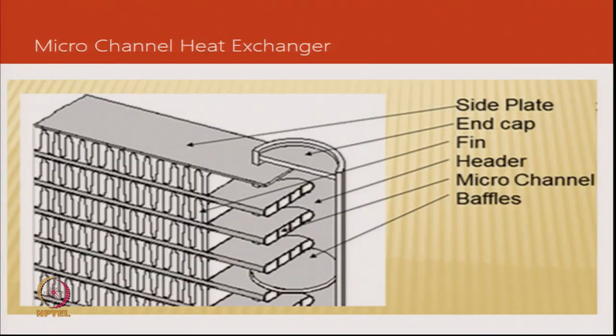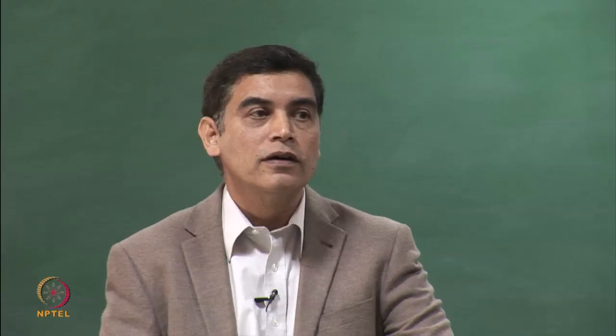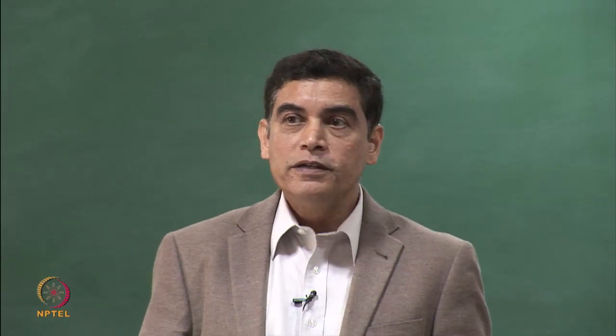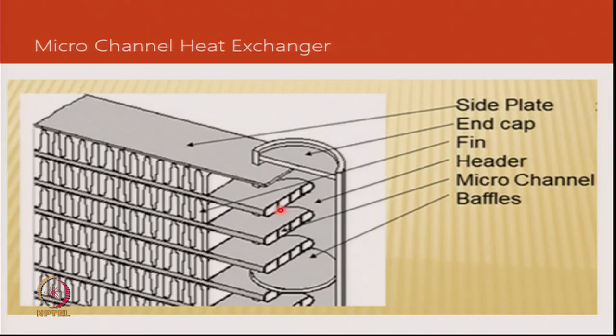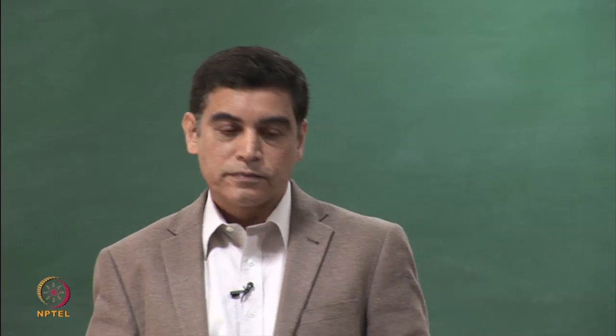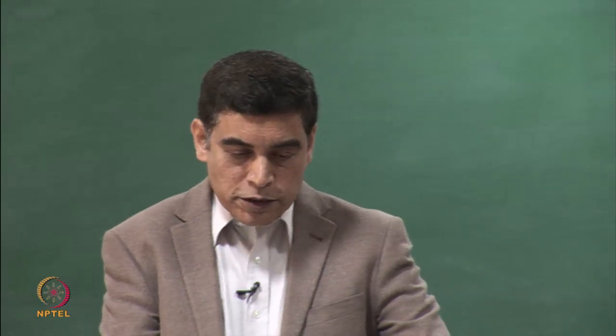Inside a micro-channel heat exchanger, there is a header into which refrigerant enters and is then distributed into different channels. Each strip has micro-channels within it — small openings inside a tube through which refrigerant is pushed using compressor pressure. Baffles equally distribute the refrigerant across the whole cross-section of the heat exchanger.